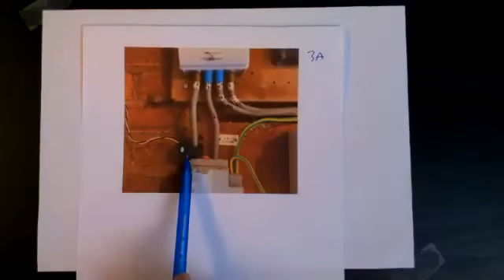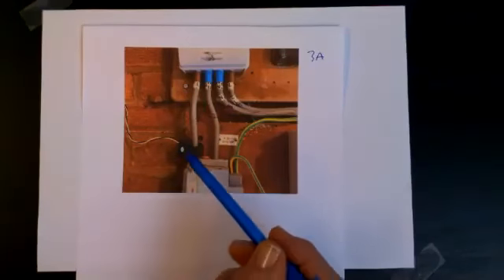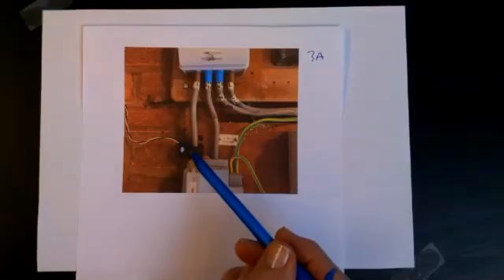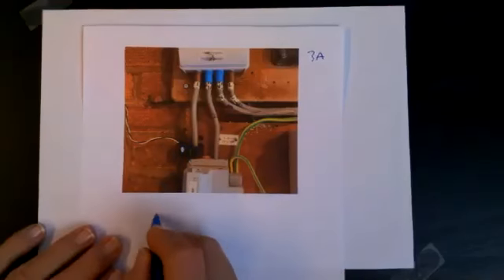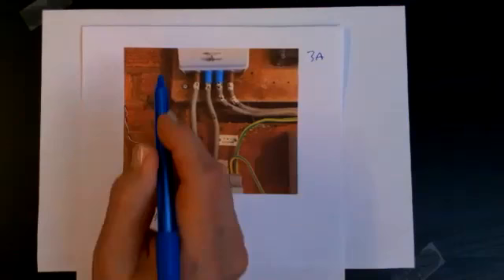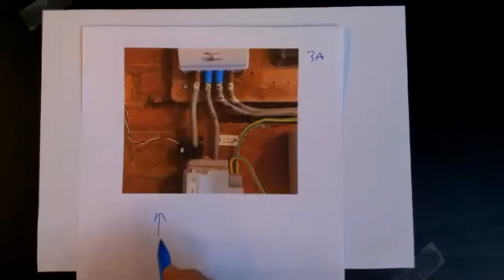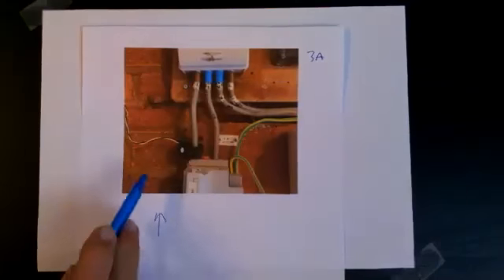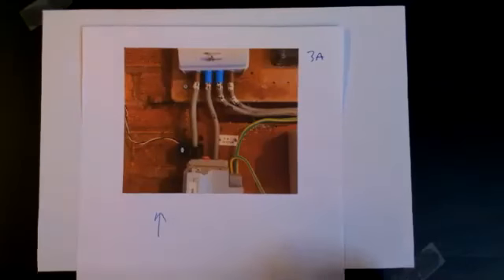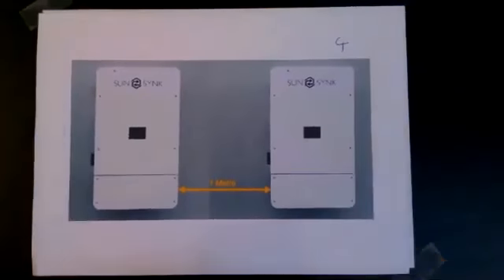So the CT coil, and also remember the direction of the CT coil. I'm going on a little bit about it because I always have issues. This is the CT coil. It mounts here on the main fuse coming in; it must be on the main fuse. Ensure the direction arrow on the CT coil faces towards the inverter. You just see a small arrow, and that goes towards the inverter. This is so important, and I keep going on about it, so I may come back to it again. So going forward, just literally mounting the inverter.